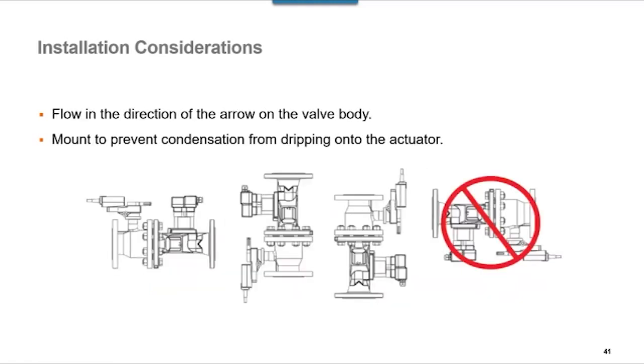Second thing, how do you install it in the pipe? Well, just like all electronic valves, I don't want the actuator below horizontal. You don't want condensate to be able to roll back into the electronics. You can mount them vertical. I see a number of these valves mounted in vertical runs because it's much easier to get the 5 straight pipe diameters, but it doesn't matter. Flow can go up or down. It's not going to affect the flow meter in either way.